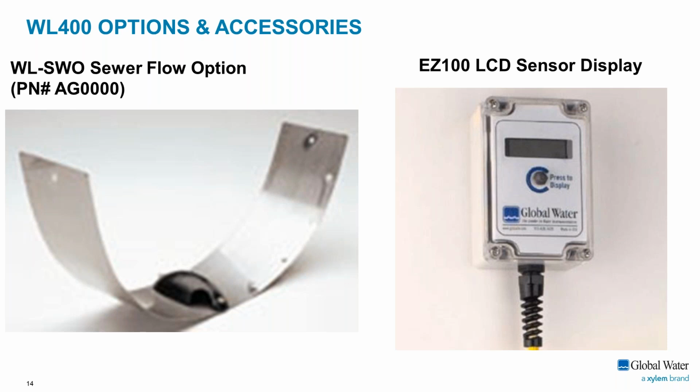It's meant for sewer application, or if you're getting into a vault down in a manhole and you have a sewer pipe and you want it to be held in place, this can actually be mounted into the pipe or an open channel flume or weir of some kind and hold the sensor in place so it doesn't get lifted up in a high velocity event. We have the EZ100 display here, which is available battery or AC powered, and basically displays your water level readings.